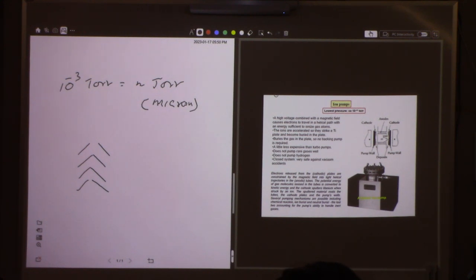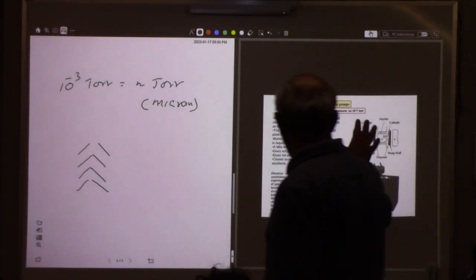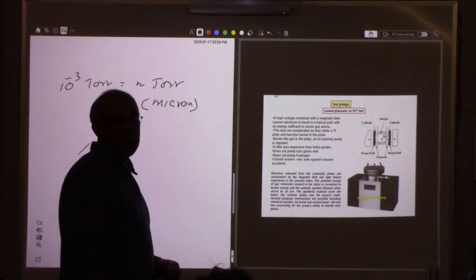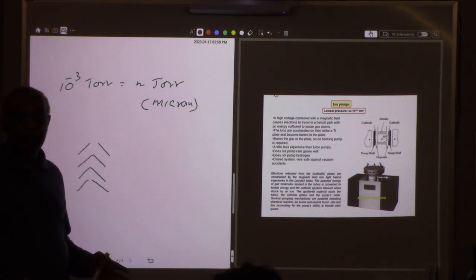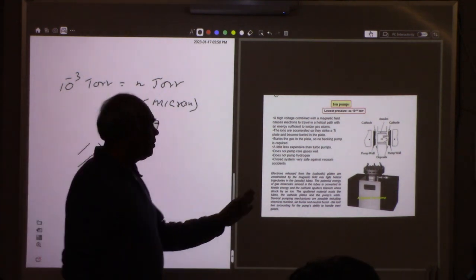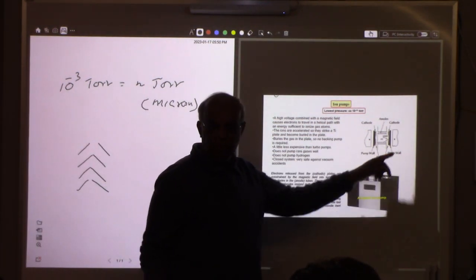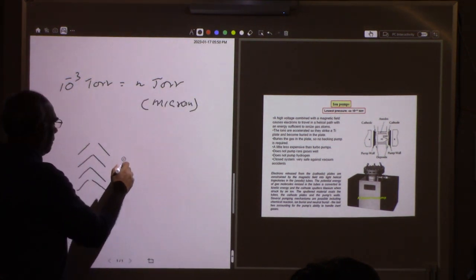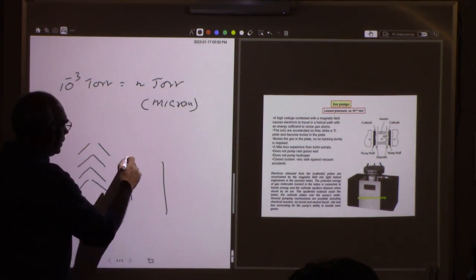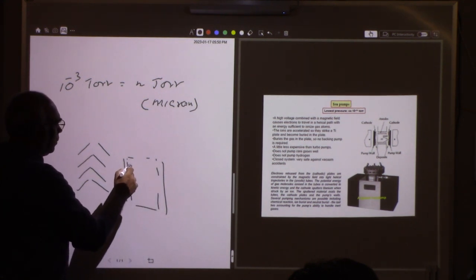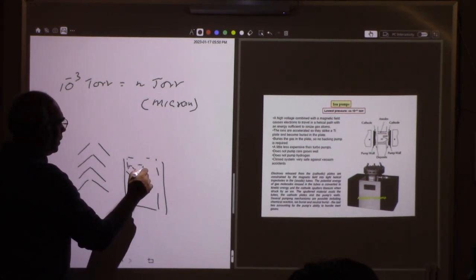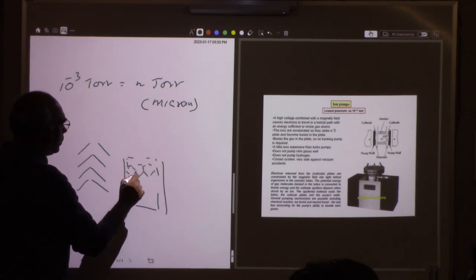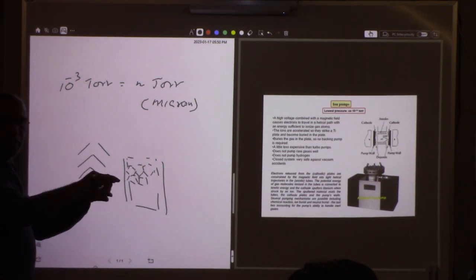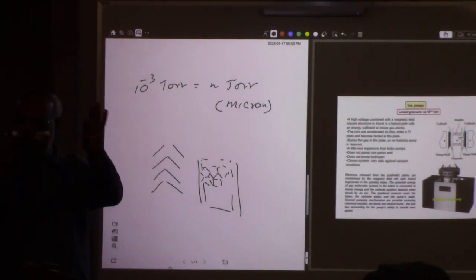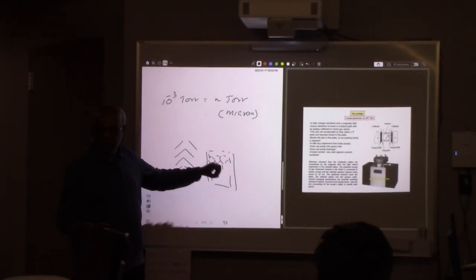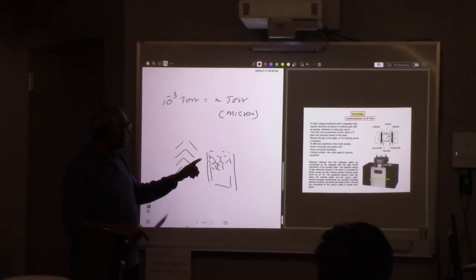So the next one is the ion pumps. This is interesting. With ion pumps, you actually don't need a backing pump because this is so clean. The only thing you have is this: we call them the cathodes. You have these two cathode plates, and then we have the anode. This anode is made of titanium tubes, arranged in a hexagonal honeycomb kind of structure.